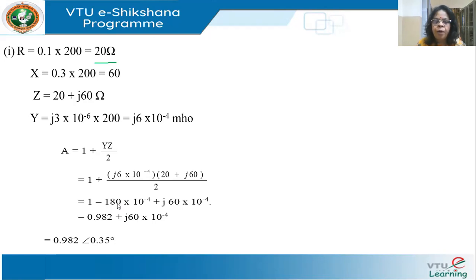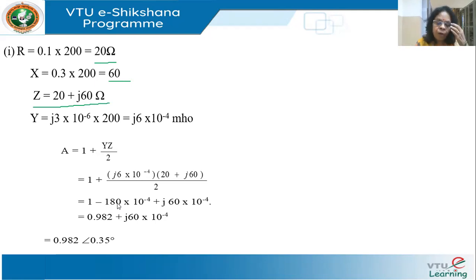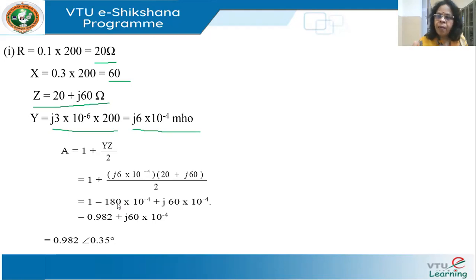R = 0.1 × 200 = 20 Ω. X = 0.3 × 200 = 60 Ω. Therefore Z = 20 + j60 Ω. Y = j3×10⁻⁶ × 200 = j6×10⁻⁴ mho. Be careful to use complex numbers throughout — A, B, C, D are all complex numbers. Students often make the mistake of using magnitudes only. In the T model: R/2 = 10 Ω, X/2 = 30 Ω on each side, and admittance Y at the center.